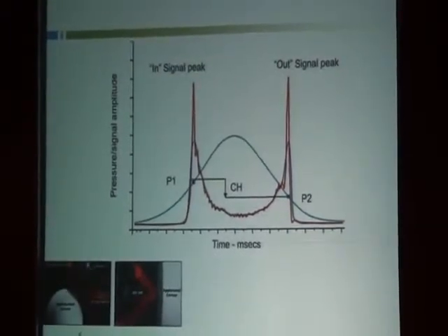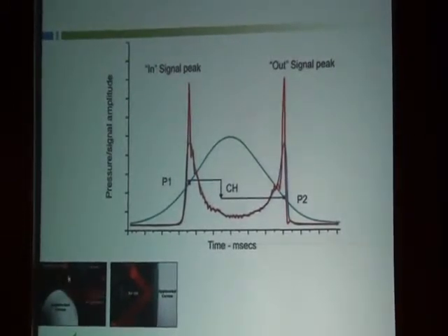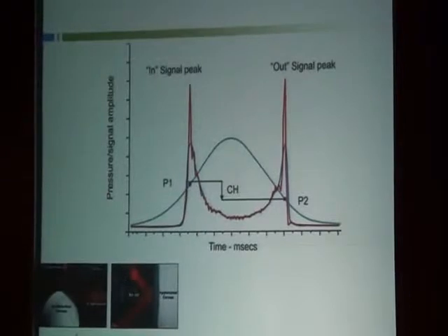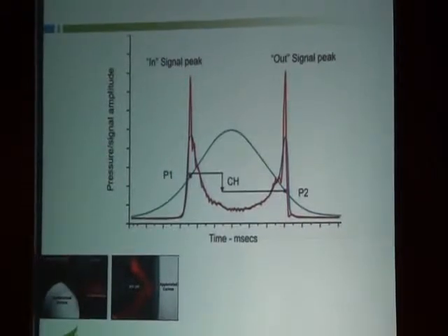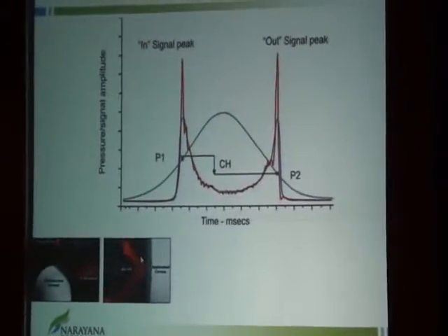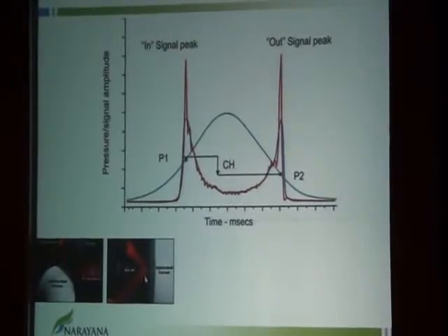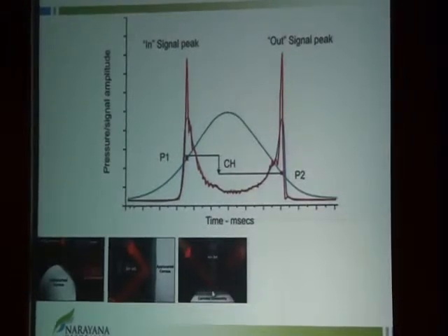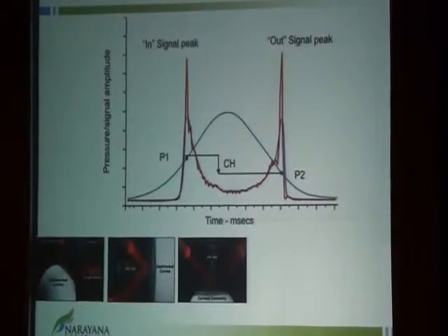This is the air jet that gives a very precisely metered, collimated air pulse. There is a light emitter and a light detector, and using this electro-optical system, it exactly measures what is happening to the amount of light that comes from the corneal applanated surface. So the air pulse has now moved the cornea from its normal surface to the position of applanation. The air pulse continues, and the cornea then goes into a point of concavity. Beyond the applanation, it goes into concavity. And now the air pulse is stopped.